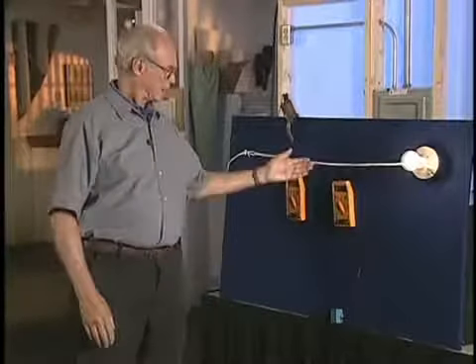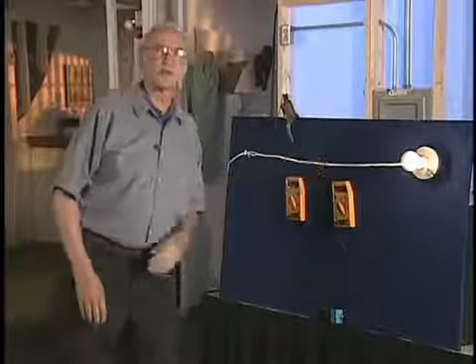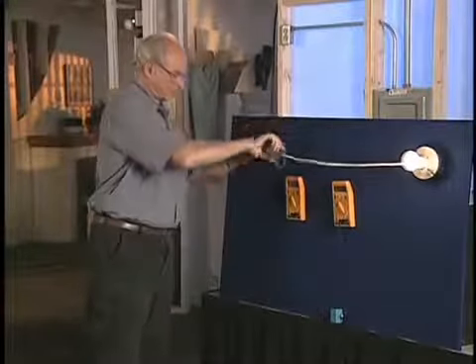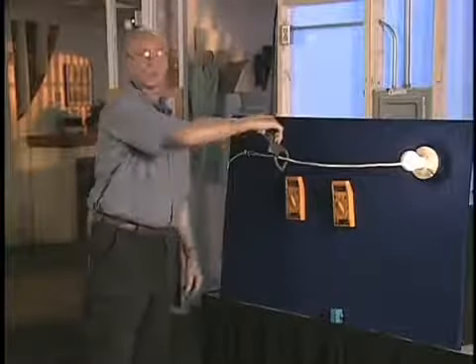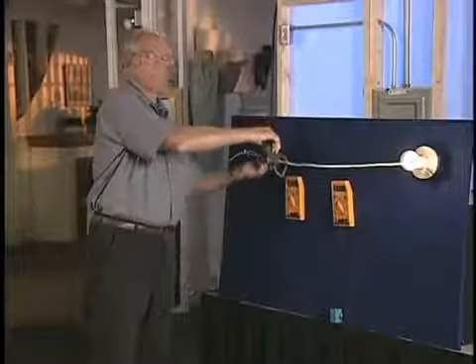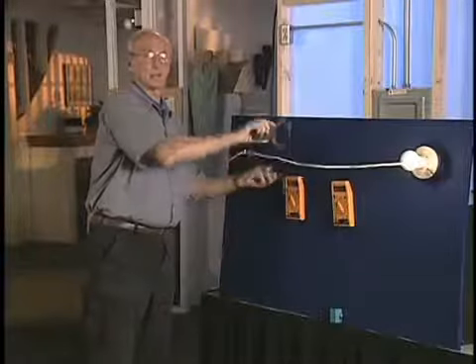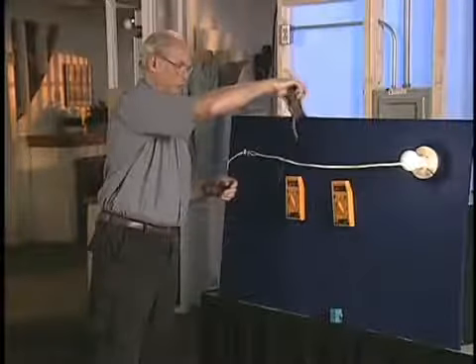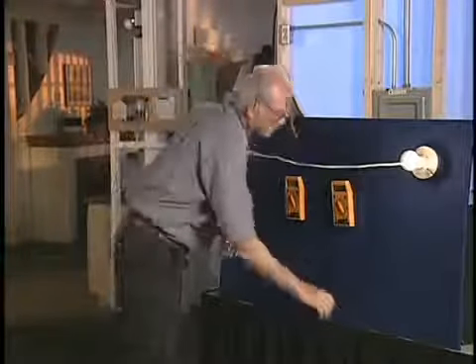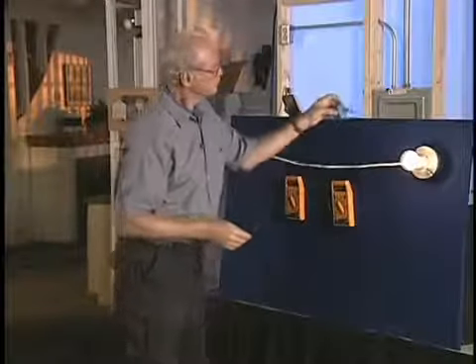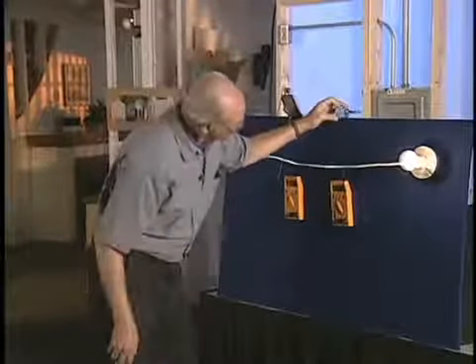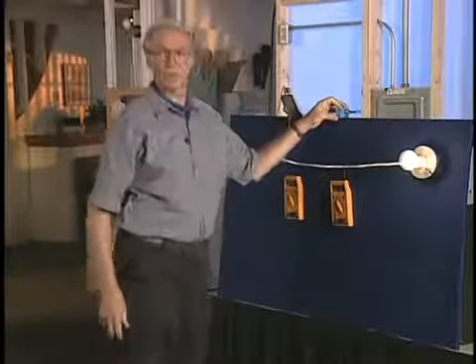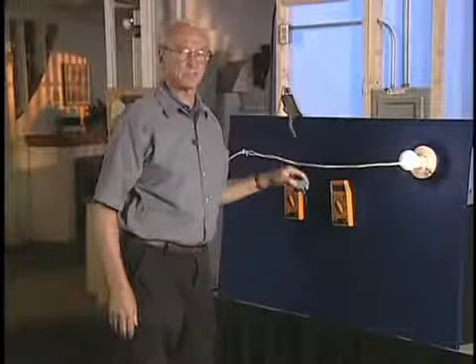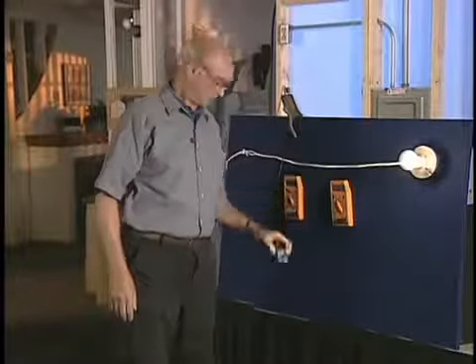Now let's measure an actual circuit. Here we have a simple circuit. We clamp our ammeter around the zip cord and see 0 amps net current. Now if we place a Gauss meter probe 6 inches away from the conductors, we will read 0.3 of a milligauss. A milligauss is a unit of measure for magnetic fields.